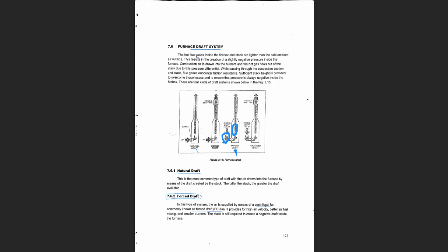Why? Because once you have a combustion process taking place, the flue gas is much lighter in density. كثافة الغاز اللي طالع، اللي هو CO2 والwater vapor، حرارته عالية، كثافته منخفضة. فالغاز اللي كثافته منخفضة دائما يطلع وين؟ للأعلى. فالآن إذا طلع هذا الغاز لابد أن في شيء يدخل مكانه، فاللي هو منه؟ الهواء البارد، يعتبر بارد مقارنة بالفلو جاز. Because of this, air will flow naturally into the furnace. طبعا من النادر جدا أنك حتلقى industrial furnace بهذا النوع اللي هو الناتشرال درافت.